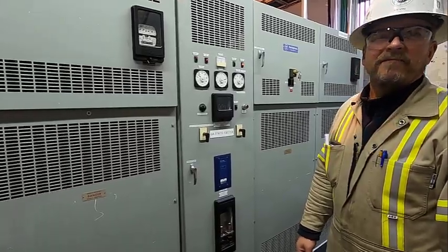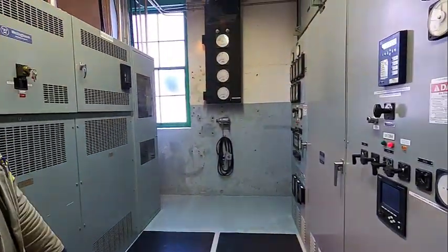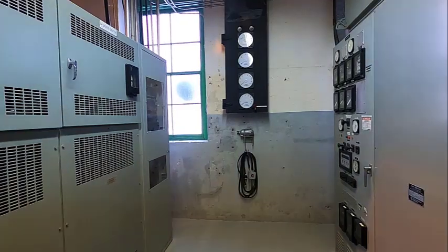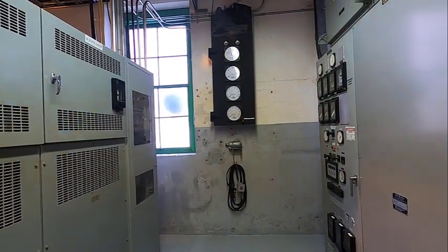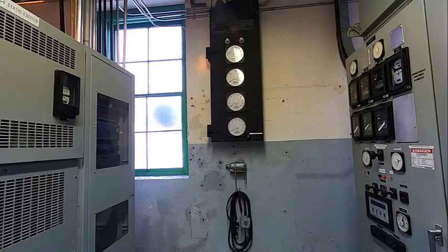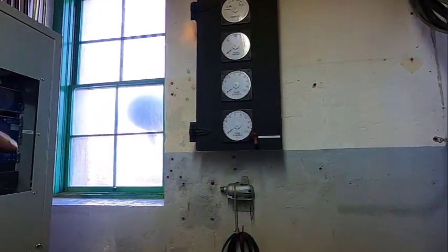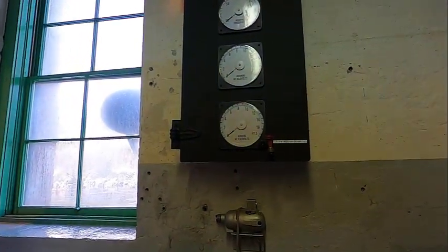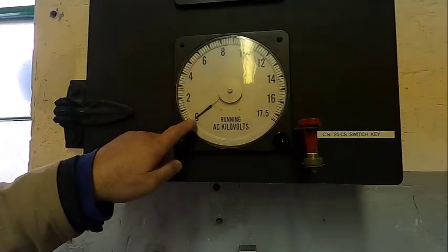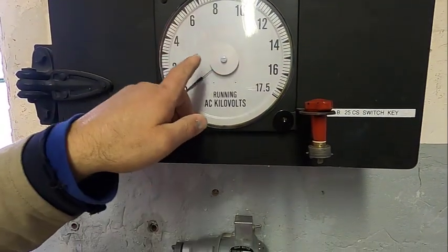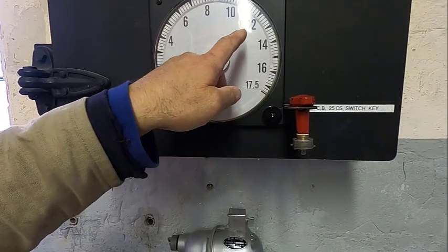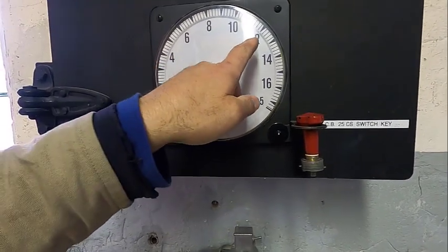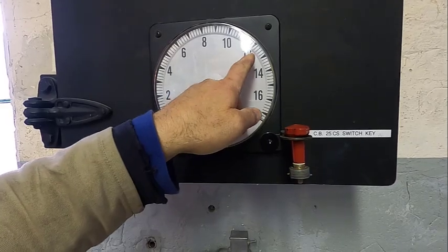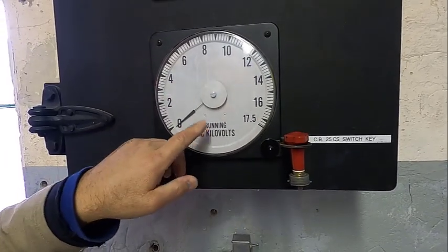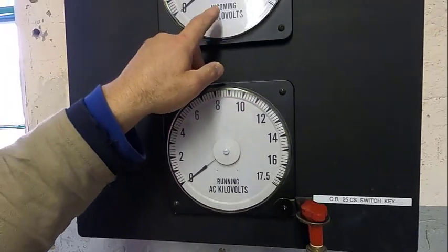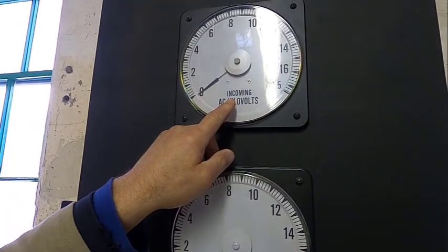And what's behind you? What's behind me is what we call a synchro-scope. So to put a unit online, we have to match the AC sine wave to that of the grid. So this is the running AC volt, so that's the voltage times 1,000 for the grid. Typically, like I say, we're going to close in just over 12,000 volts. So that's running, that's the system. Incoming is whatever generator we've selected to put online.